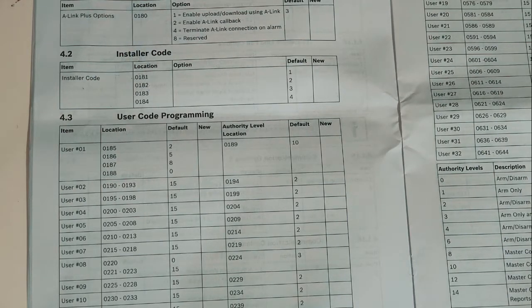The installer code has four digits, so the first digit of the code is stored at 181, and the default values are over here. So when you default the panel, these default values are what are now programmed into the system. The first digit of the installer code is located at 181, and by default it's a 1. Second digit is at 182, third at 183, fourth at 184, so 1234. What we're going to do now is reprogram the installer code from 1234 to 5678. To do that, I've got to jump to location 181. Does that make sense? I hope that makes sense. I might be making this sound more complicated than it is.